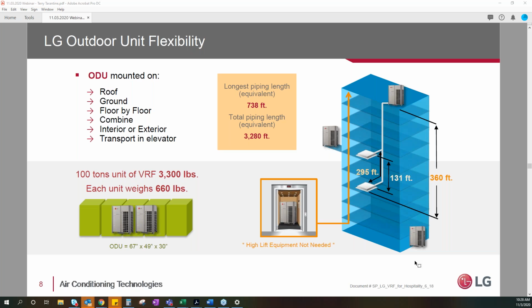We can run a long way as well, and this also applies to water source heat pumps. Water is easy to pump, refrigerant's even easier to move around the system. Here this manufacturer is showing that we can go 738 feet on a run, with a total equivalent piping length of 3,280 feet. So we can cover an awful lot of distance off of one small unit.